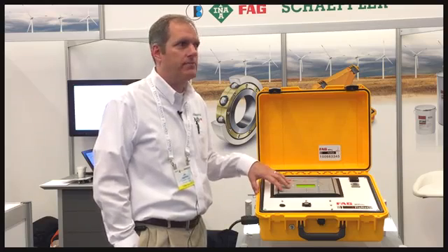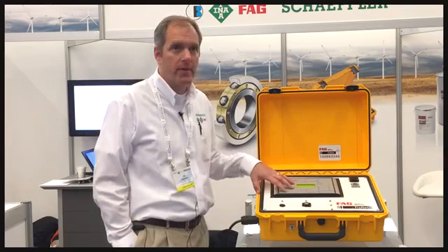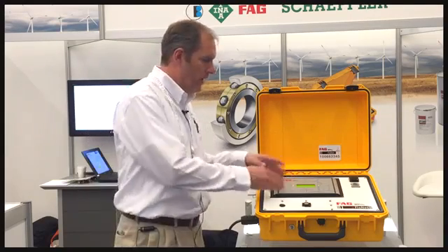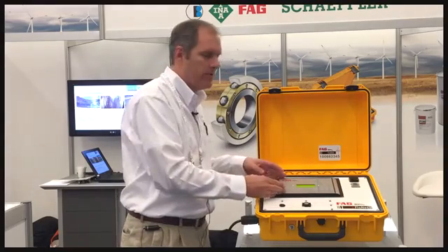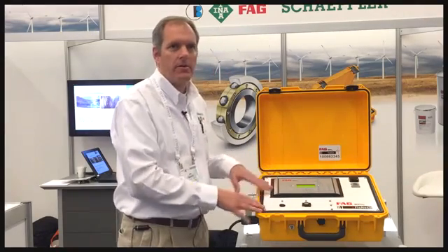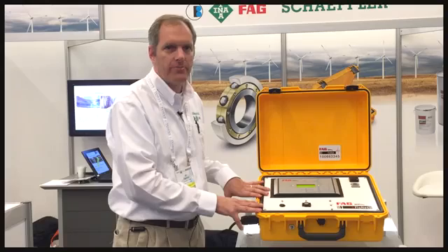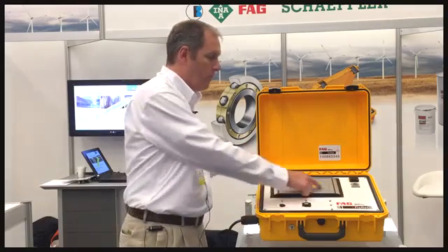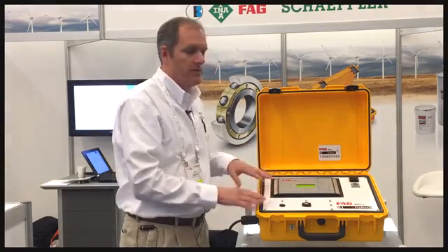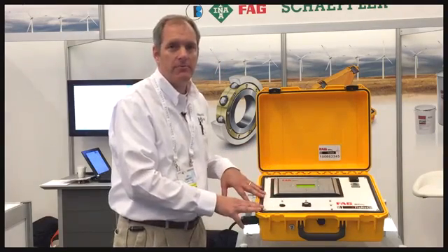Well, hey, I'm Jim Ingerslew with the Schaeffler Group, and we're going to talk about the WiPro M. This is the first device where we're using condition monitoring to monitor a wind turbine, but we're doing it in a mobile way. So typically people would take a WiPro like this, this component here, they would put one on every turbine. And what we've been finding is as we talk to different customers, they say, well, I don't have enough money for one of these for every turbine, but they still want the benefit from vibration analysis.